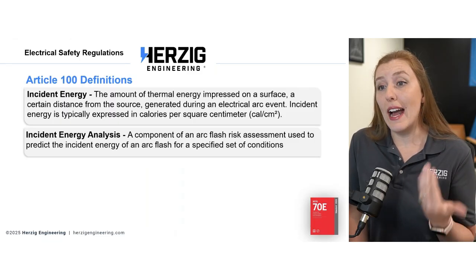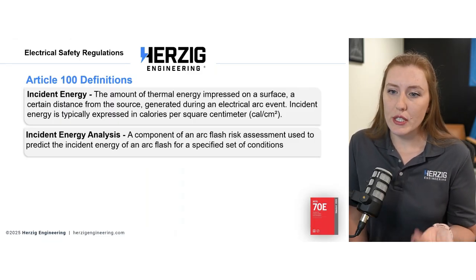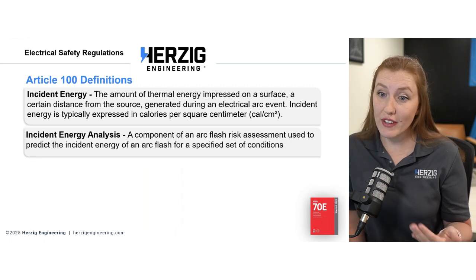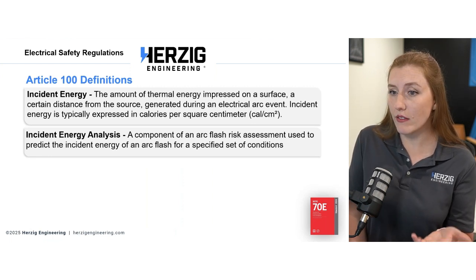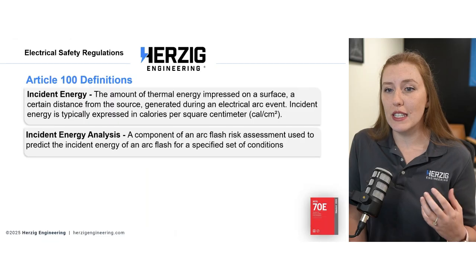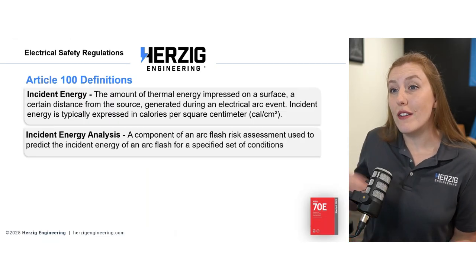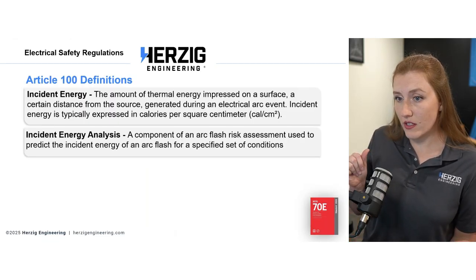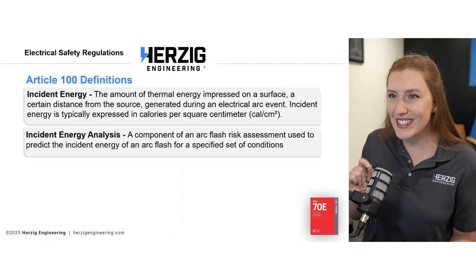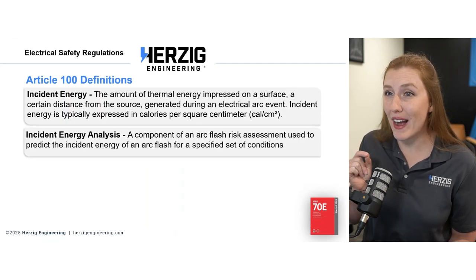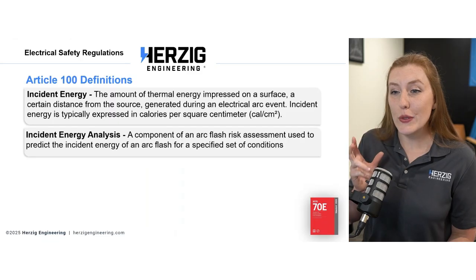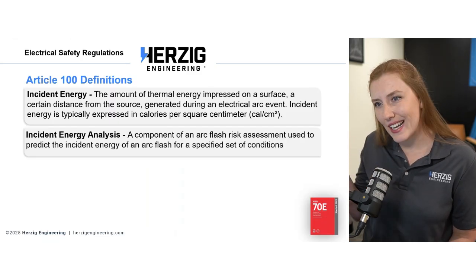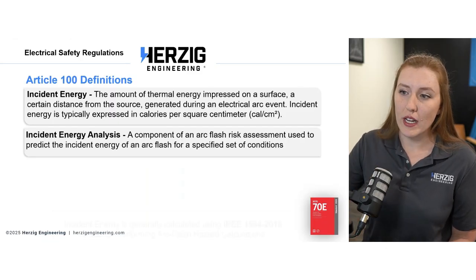The incident energy analysis is a way of predicting that arc flash severity. So it's a component of arc flash risk assessments used to predict the incident energy of an arc flash for a very specified set of conditions. Specified set of conditions. I'm going to circle back on that a couple times because as soon as those conditions have changed, you've got to have that study reviewed and re-updated.